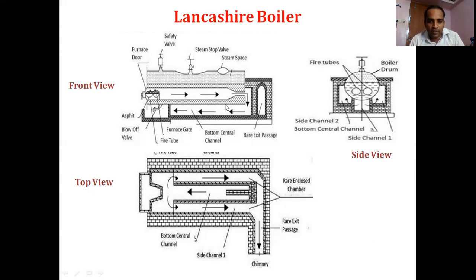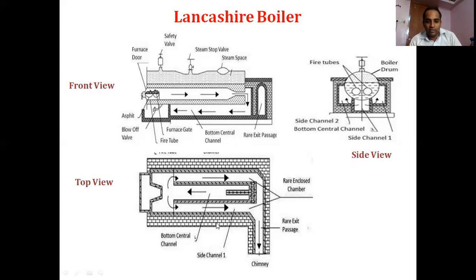The Lancashire boiler has the same parts studied in the Babcock & Wilcox boiler: a steam stop valve, safety valve, furnace door through which fuel is fed inside, ash pit for collection of ash, blow-off valve to remove mud particles from the water, furnace grate for combustion, one bottom channel and two side channels which control the flow of hot gases coming out of the two tubes, and a rear exit passage leading to the chimney.